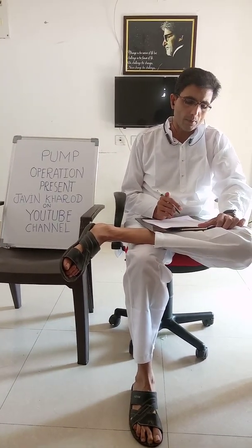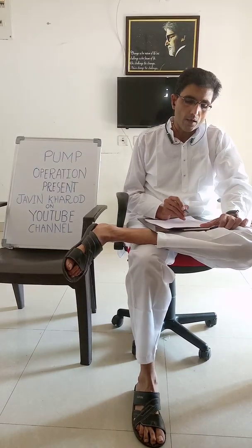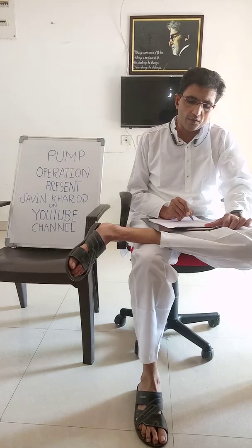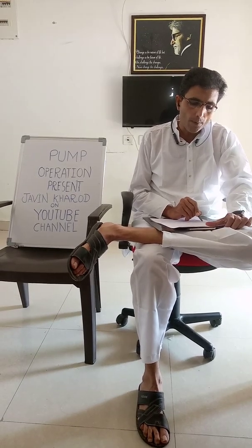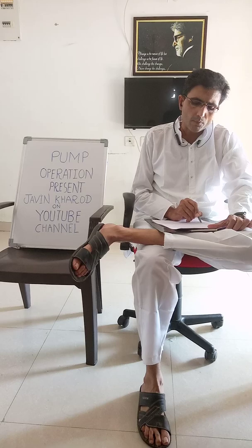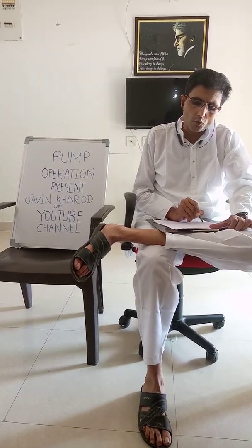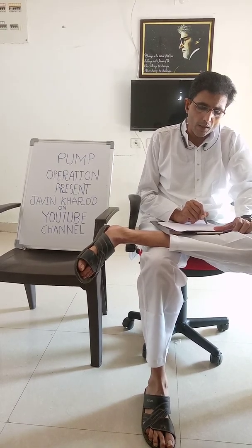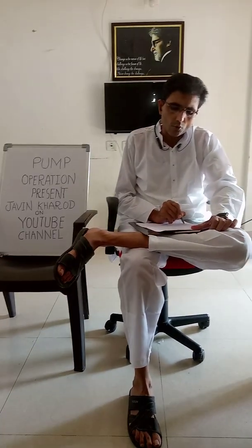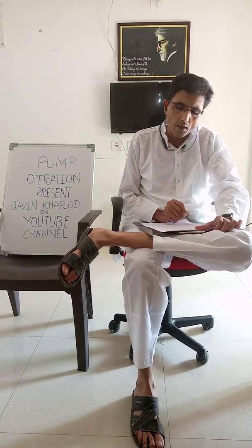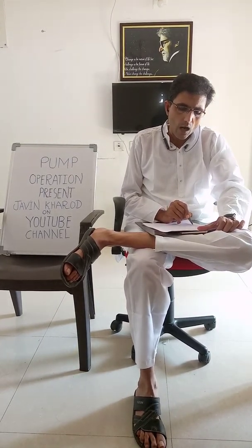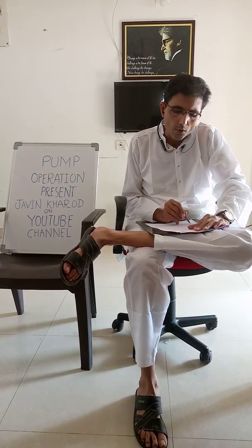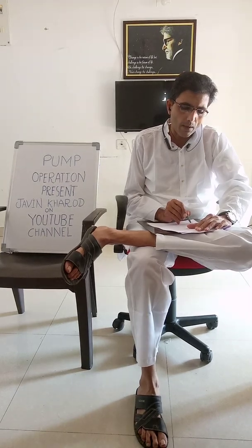Now, centrifugal pump. A centrifugal pump is a rotodynamic pump that uses a rotating impeller to increase the pressure and flow rate of a fluid. Centrifugal pumps are the most common type of pump used to move liquid through piping systems. The fluid enters the pump impeller along or near the rotating axis and is accelerated by the impeller, flowing radially outward or axially into a diffuser or volute chamber, from where it exits into the downstream piping system.